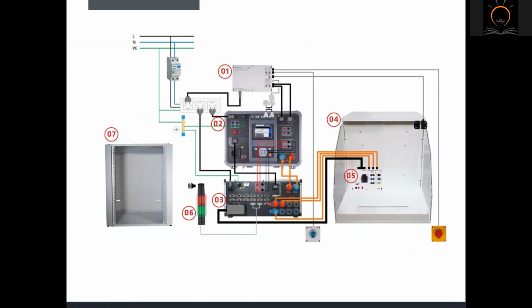For a better understanding of the upcoming slides equipped with technical data of different components, we will first go separately through the specific components of the available test system. Under the serial number 1, there is a safety module. This can be a module equipped with an RFID sensor, light curtain, two-hand control, or a safety module with current limitation. All of them are connected to the same connection ports on the instrument and are therefore protecting the operator of the test station from electric shock.